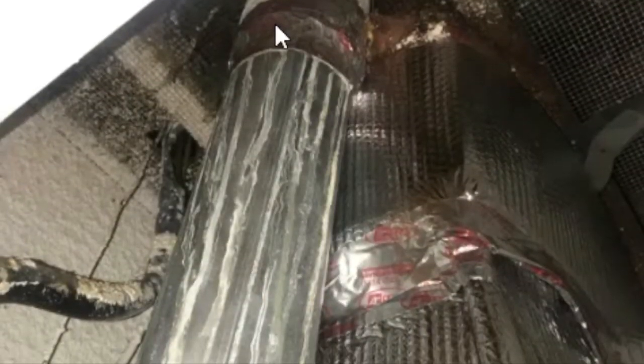The existing furnace vent stack had been connected to a transite vent stack, which went through the attic and to the outside. The problem with transite, it's an asbestos type material that has a problem with condensation. You cannot install an 80% furnace to this type of venting.